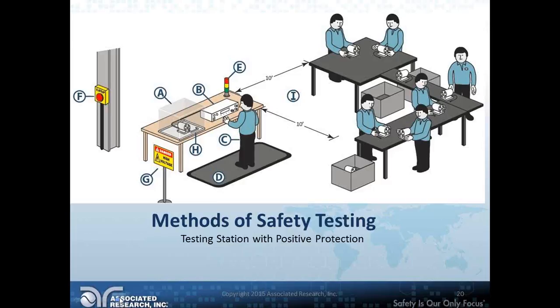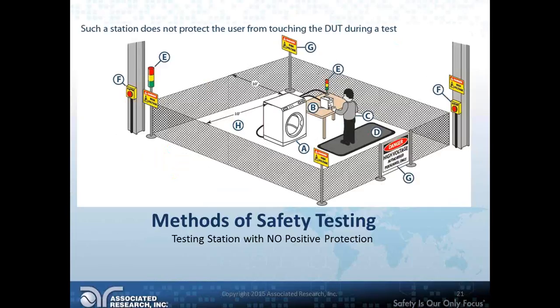But not every DUT can fit in an enclosure. What if you're testing an entire dryer or washer? You'd need a pretty big enclosure for that. So we also have stations with no means of positive protection, meaning there could be exposed conductors. That's a station that looks like this, with the same safeguards in place: signal lights, high voltage warning signs, and a prohibited testing area sign labeled G at the front.